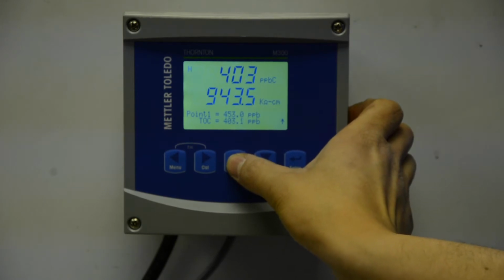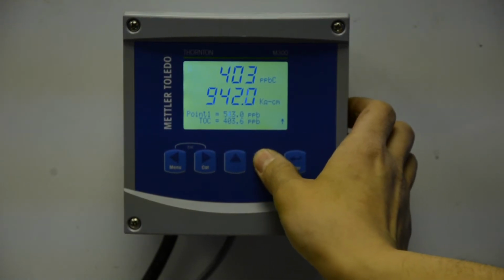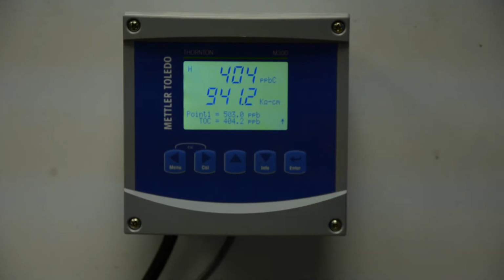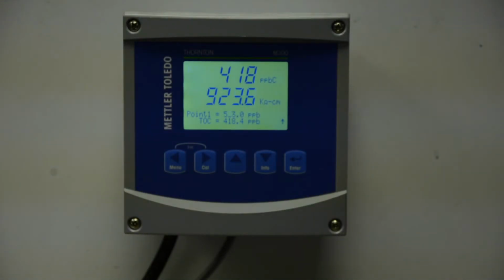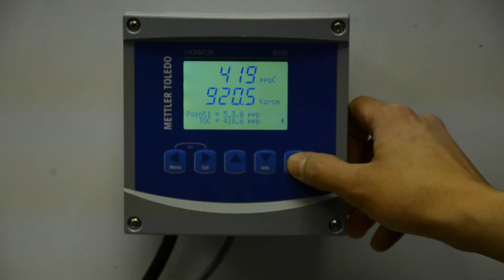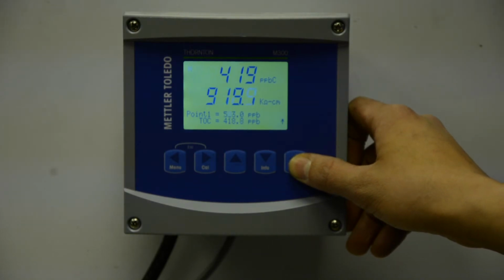Now it'll ask you what your point 1 calibration is going to be. On this unit, we're going to change it to 513 parts per billion. That's the solution that we have that it's certified at right now. Then underneath it shows you what it's currently reading, which is 406 parts per billion. That's adjusting a little bit. And you will have some variation, a little fluctuation as you're performing this. Once your solution stabilizes, press Enter to perform the calibration.